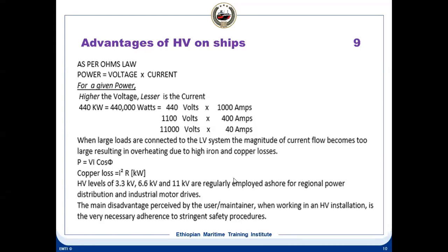So suppose a generator system, a low voltage system with a voltage of 440 volt, has to deliver 440 kilowatt. It needs to cater for 1000 amps. So the current is going to be very high. If a 440 volt system has to deliver 440 kilowatt, the current is going to be 1000 amps. So you can see, when large loads are connected to low voltage systems, the magnitude of the current becomes too large.